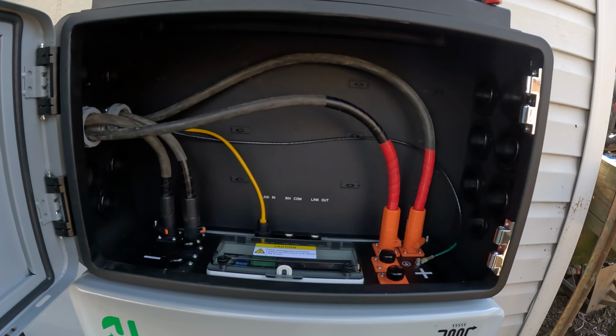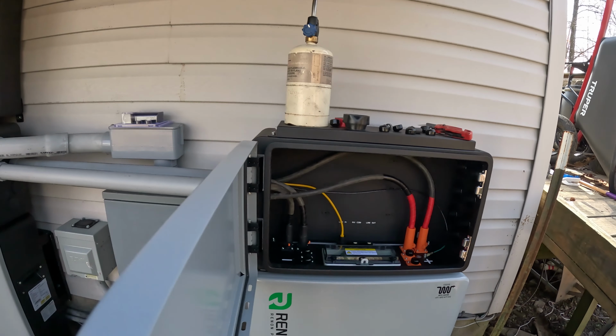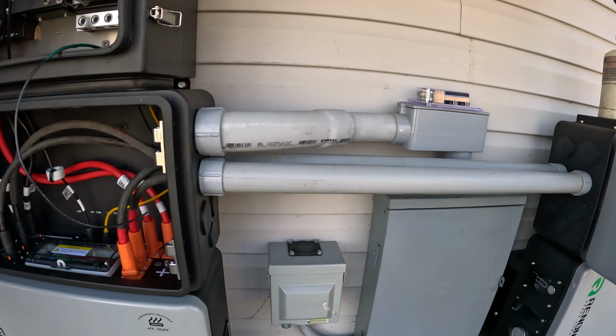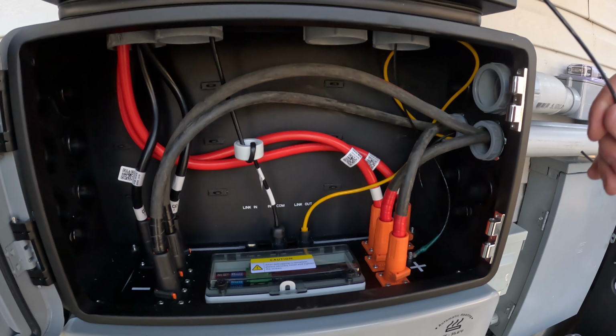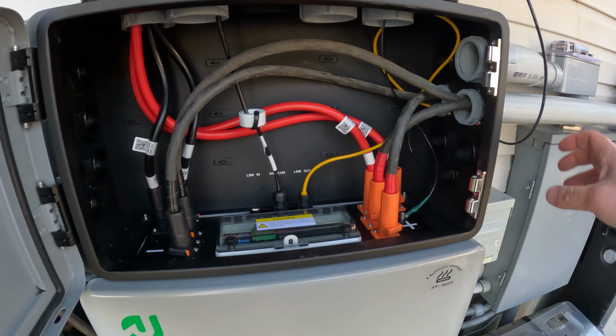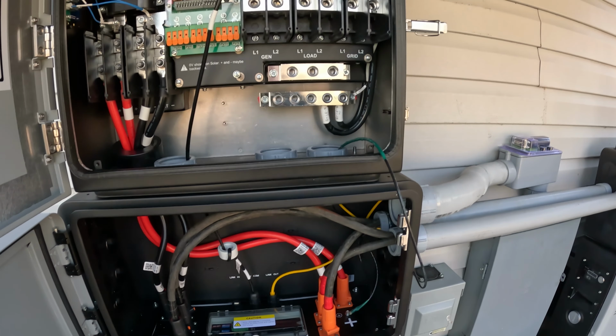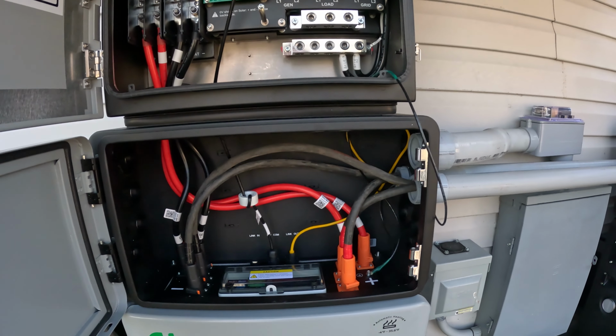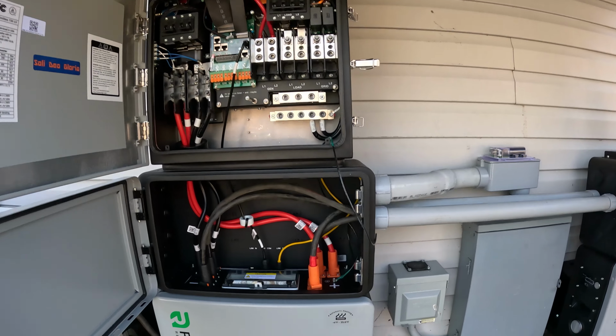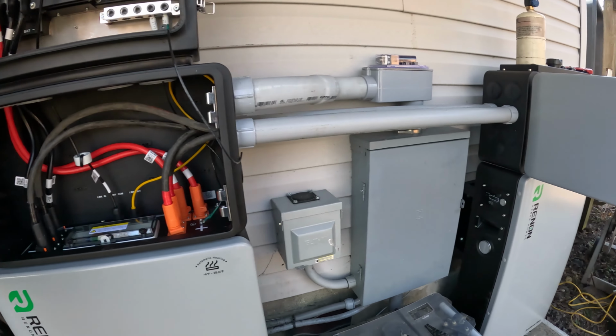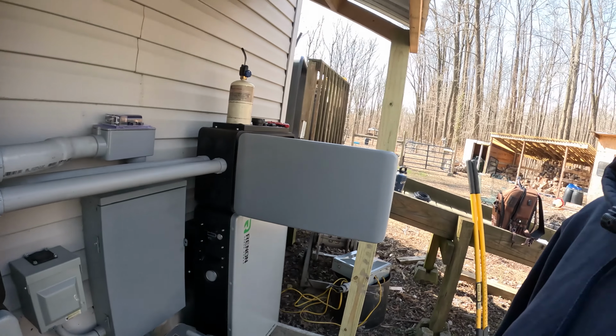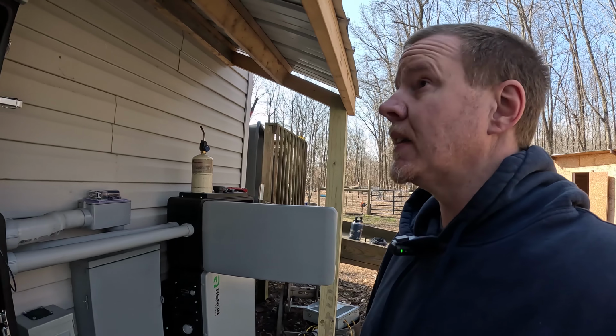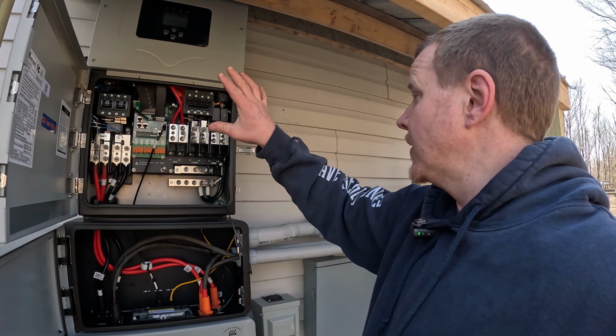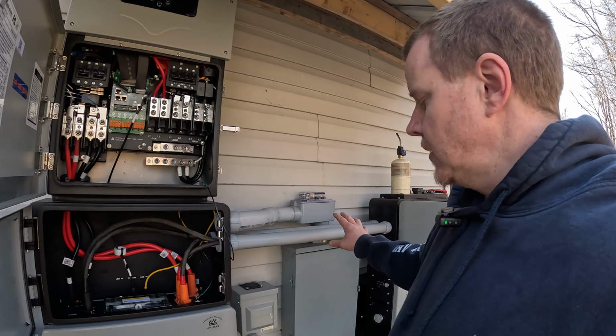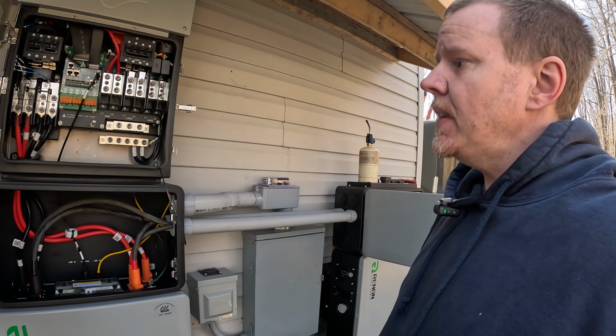Well, we've got all of our DC conductors ran, our communications lines in, and our ground conductors ran for just equipment grounds. So now what we've got to do is fire up the inverter and make sure everything's set and communicating with the batteries. Then we should be good to go on and start tying in the load and grid side to our panel down here.